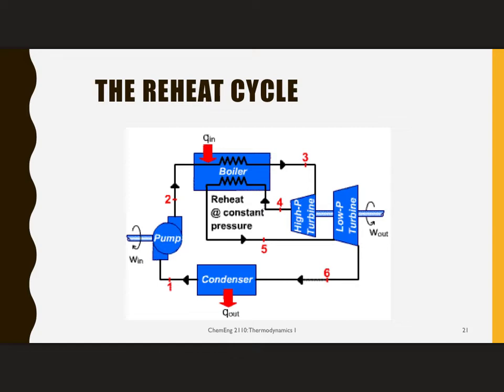But before it gets to that dangerous region of the saturation curve, we're going to take it out of the turbine and run that same fluid back into the boiler for a second pass. That is sometimes called a reboiler, that portion of it. Then we come out of the boiler and back into the rest of the turbine.